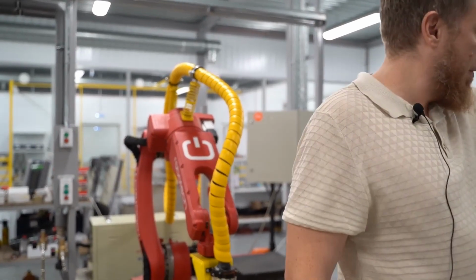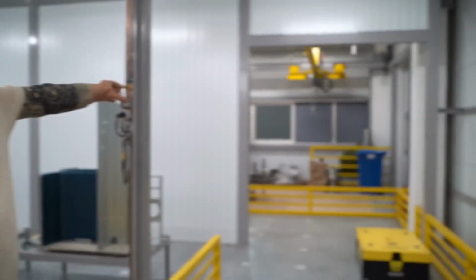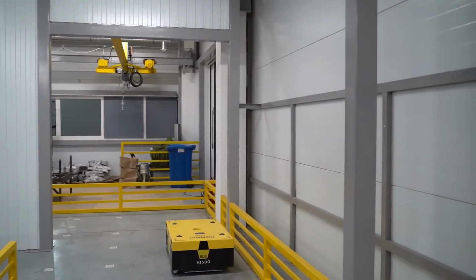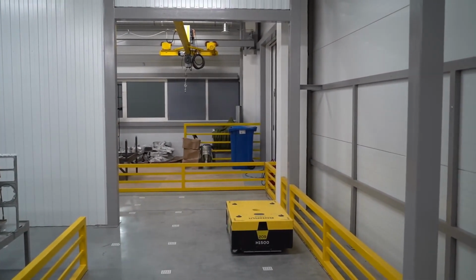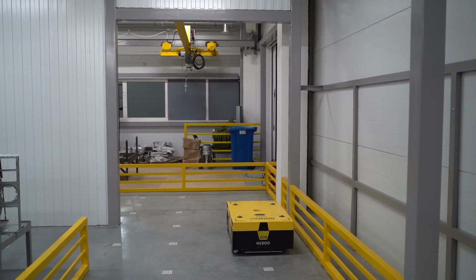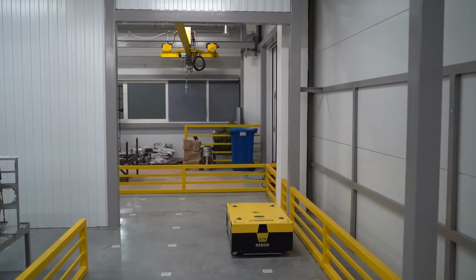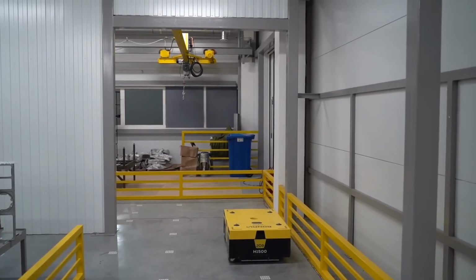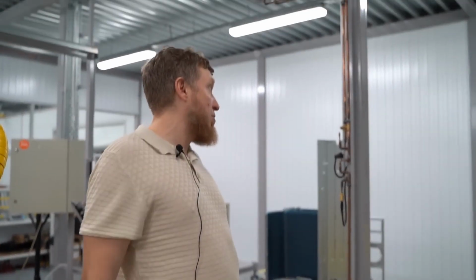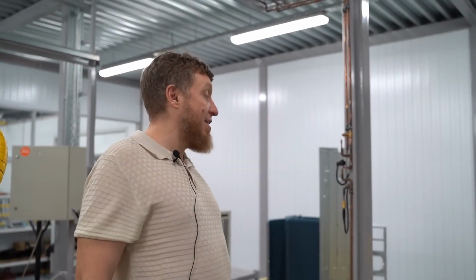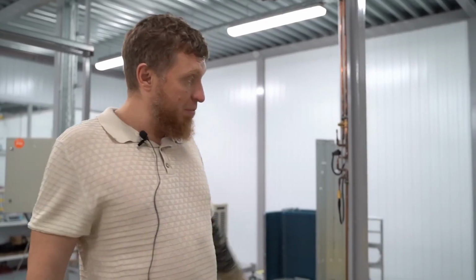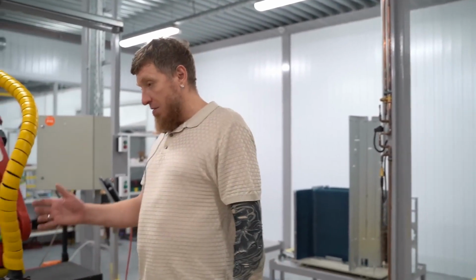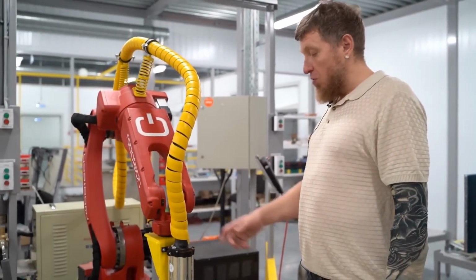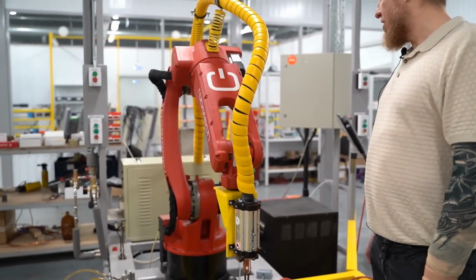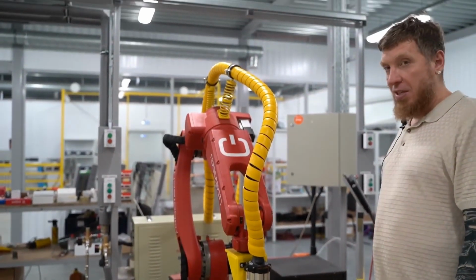So, gentlemen, we are now near the area for automatic soldering of the Freon circuits. How does this work? In that area, a person manually assembles the Freon circuit. He has pre-bent pipes, fittings, and instead of soldering, he puts on soldering rings and places the assembly onto this automatic cart using a hoist to position it. He moves the unit into position for soldering. The cart moves up here to this robotic arm, which has an inductor clamped in it, and according to the program, it solders all the connections.